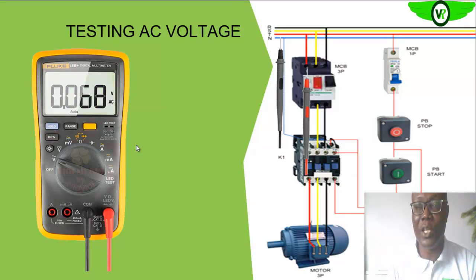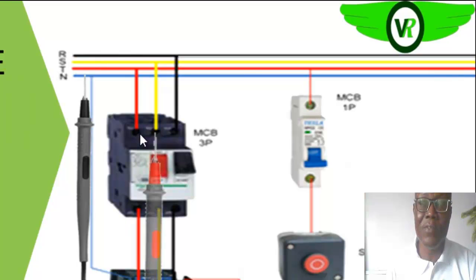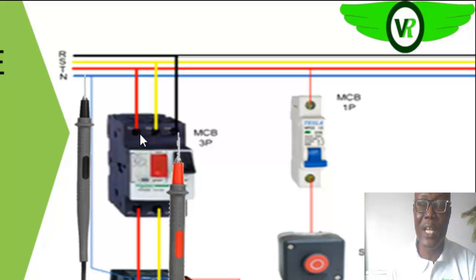Okay, so on this you have the first line, line 1, 220 volts. So neutral to line 2, you also have 220 volts. Neutral to line 3, you also have 220 volts. So if the voltages are not the same on each of these phases, it means that we are having a problem. We are having a challenge. Okay? Now let us assume that the voltage is the same. What it means is that we have input to our circuit breaker.